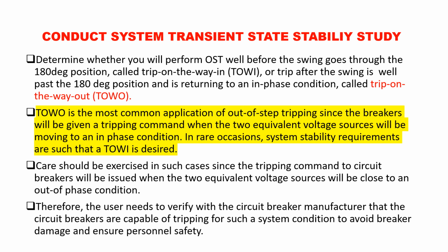So one thing I will mention here, that power system study, whether steady state or transient state stability, is not an easy topic, and the relay setting for power swing blocking and out-of-step tripping, I mean the islanding, is not an easy task. Even after many researches and inputs from the field and theoretical and mathematical modeling, it is a very difficult phenomenon, in the case of a large disturbance, to save the lines and the power system. You can always see and read reports all over the world that it's not an easy task. And even after working in the field for 30, 40, 50 years, you will witness that system breakdowns on a large scale keep on happening.